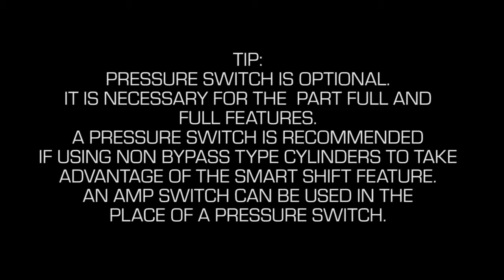It is necessary for the part full and full features. A pressure switch is recommended if using non-bypass type cylinders to take advantage of the smart shift feature. An amp switch can be used in the place of a pressure switch. Set pressure switch. We typically set the pressure switch at 150 to 250 psi below relief pressure.